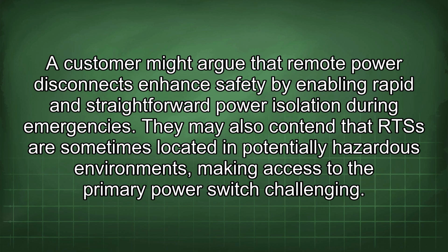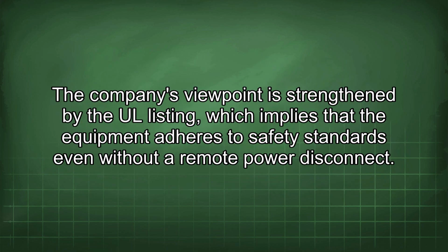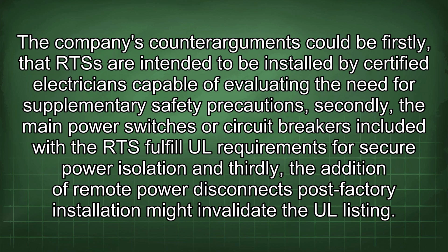switch challenging. The company's viewpoint is strengthened by the UL listing, which implies that the equipment adheres to safety standards even without a remote power disconnect. The company's counter-arguments could be, firstly, that RTS are intended to be installed by certified electricians capable of evaluating the need for supplementary safety precautions. Secondly, the main power switches or circuit breakers included with the RTS fulfill UL requirements for secure power isolation. And thirdly, the addition of remote power disconnects post-factory installation might invalidate the UL listing.